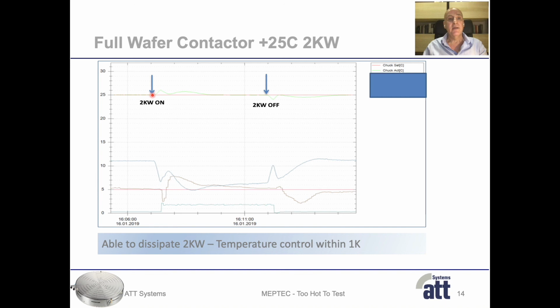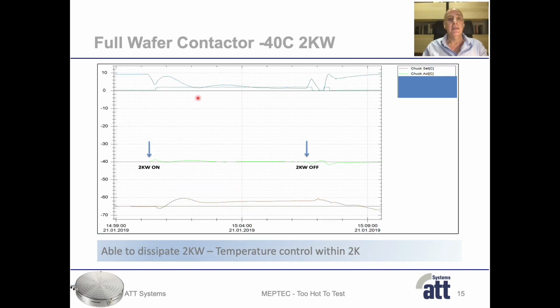What you can see is when we turn on the 2000 watt here, then the temperature will increase by around 1 degree C. And then the system is able to fully dissipate the 2000 watt and to control the temperature exactly at the set point. So this means that we are able to dissipate 2000 watt at 25 degrees C and to control the temperature within 1 Kelvin. The next slide shows the results at minus 40 degrees C. And here again, the red line is the chuck set temperature, and the green line is the actual chuck temperature.